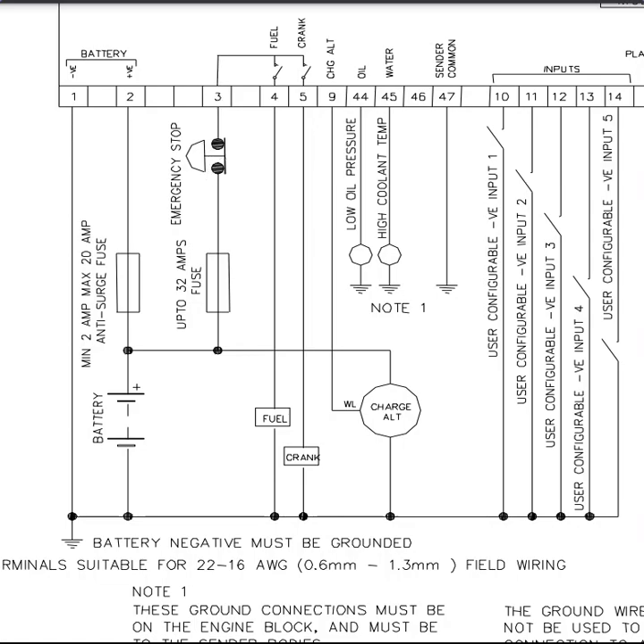When you push the e-stop, just imagine this line right here that's next to the 2 black dots will disconnect from touching the 2 black dots. So right now it's showing that voltage can go right where my mouse just went. It goes through the fuse to the black dot, then through this line, then through the black dot again. Once this black line is moved out and there's no touching the black dots, we know there's no voltage able to pass through from this black dot, because there's nothing connecting it to the second black dot.